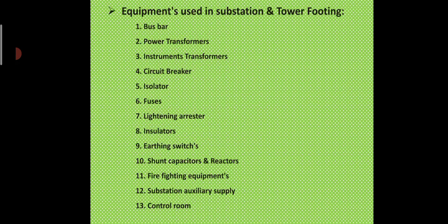Next is lightning arrester. All the equipment in the outdoor station should be protected against direct lightning shocks and traveling waves reaching the station over the transmission lines. A surge diverter bypasses the surge voltage to the earth, thus holding the voltage across protected insulations to a safe value.